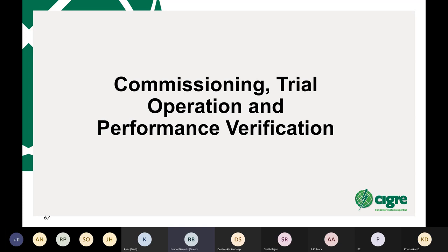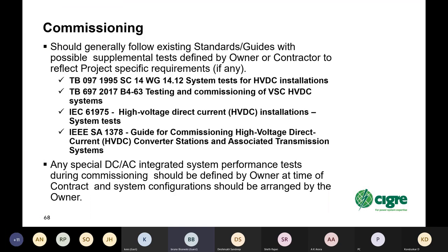Commissioning, trial operation, and performance verification. Commissioning should generally follow existing standards and guides, with possible supplemental tests defined by the owner or contractor to reflect project-specific requirements, if there are any. There's a listing of standards and testing requirements for HVDC systems given there, from both IEEE and IEC, as well as some CIGRE technical brochures that cover the subject. Any special DC-AC integrated system performance tests may not be included in those standards, and need to be defined by the owner and agreed with the HVDC contractor at contract time, so that it's sure they can be done and will be done.